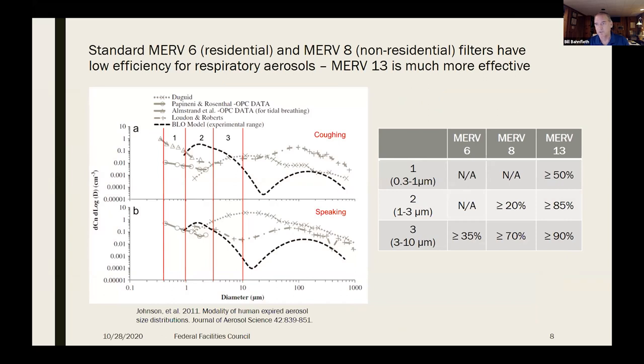And I've overlaid on it the three ranges within which the ASHRAE standard 52.2 rates a filter. So let's just look at MERV 8, which has no requirement at all to remove particles that are smaller than 1 micron, 20% for 1 to 3 microns, and 70% for 3 to 10. That's really not going to help us very much if we're trying to reduce infection risk. But if we go to the level of MERV 13 that's recommended, we now have a filter that will remove 50% at least from 0.3 to 1, 85% from 1 to 3, and 90 from 3 to 10.